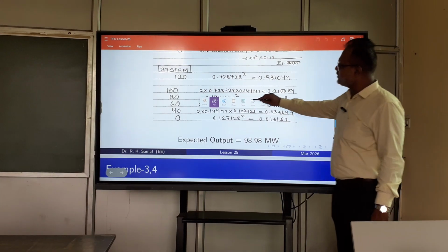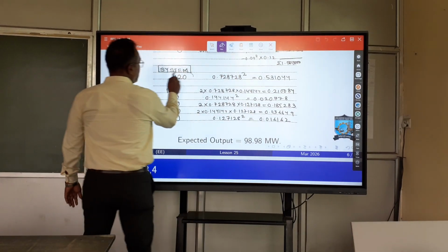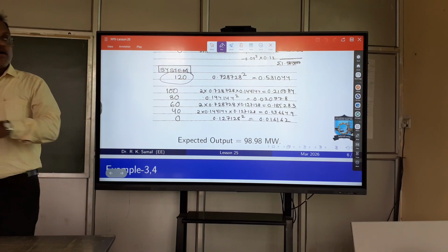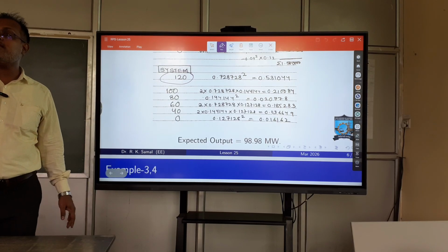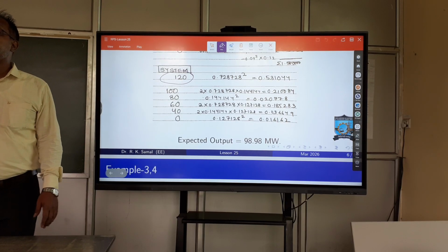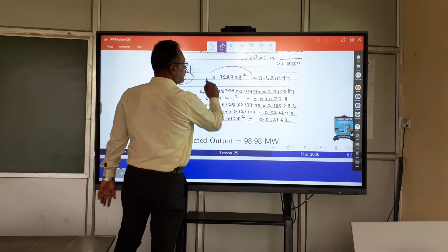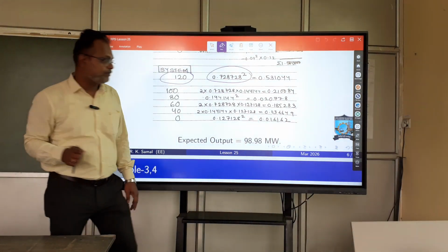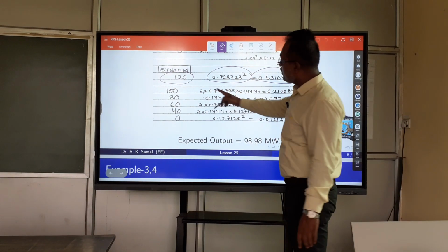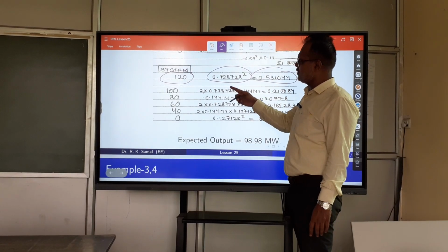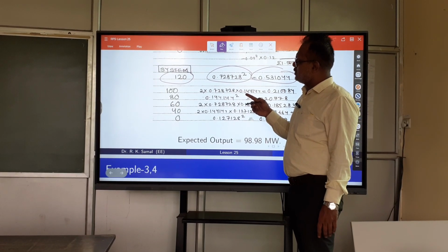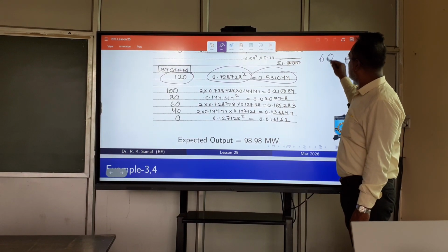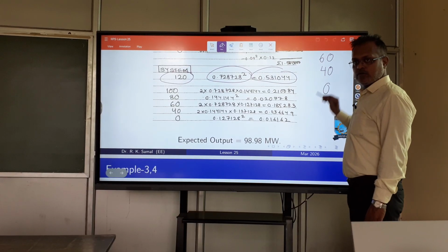So for the whole system, what is the case? The first case is available output 120 megawatt when both these systems are on. So what is the availability? What was the first case? 120 megawatt output? 0.728 squared, because both should be available. Then only the output is 120 megawatt. We have got for the unit 60, 40, 0.